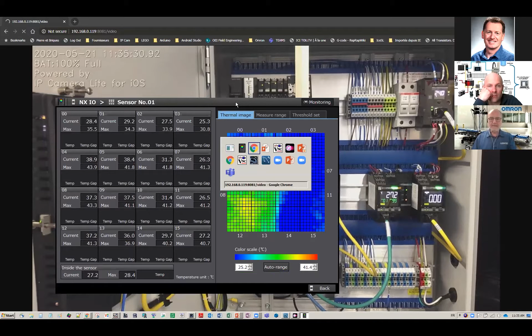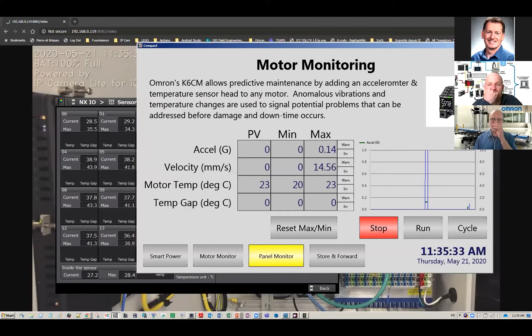Again, if we look at our panel monitor view on this HMI, we also have the ability to show you the actual picture on an HMI, giving you all the pixels back in temperature and giving you your alarms, obviously, as we need to see. So you don't have to have the application. It could be made inside your control panel by the PLC looking at the different cells. We just provide an array of points inside the PLC with all the different temperatures.